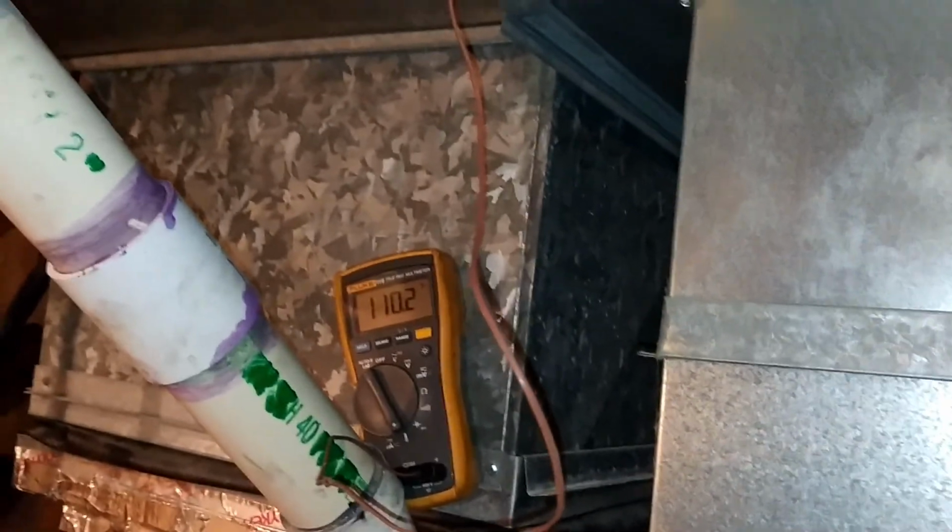What's going on with that? Anyway, we're just trying to figure out the problem. Everything looks good as long as our temp rise doesn't get crazy, and it's kind of hanging at 110, slowly climbing. What did you say the return was? 65. 65, so 35, 45. Yeah, there's no way we're going to get too hot.